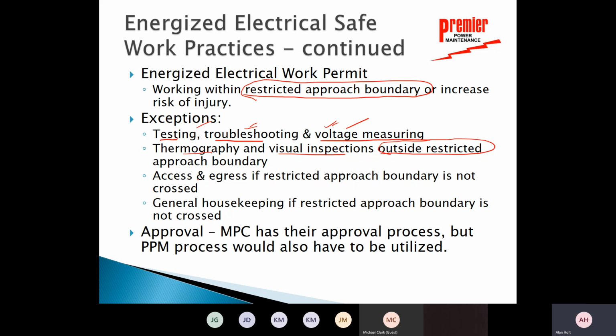And they keep adding these things: entering or leaving if the restricted approach boundary is not crossed. You didn't cross the restricted approach boundary, so that doesn't. General housekeeping, if the restricted approach boundary is not crossed. I don't understand why we're sweeping the floor, but if you don't cross the restricted approach boundary, it wouldn't require an energized work permit. I would tell you that we want to eliminate these. We don't want people who are not qualified walking in or around the equipment, even inside that limited approach boundary. And we don't want people housekeeping, even inside the limited approach boundary. Put the cover back on before we sweep the floor.